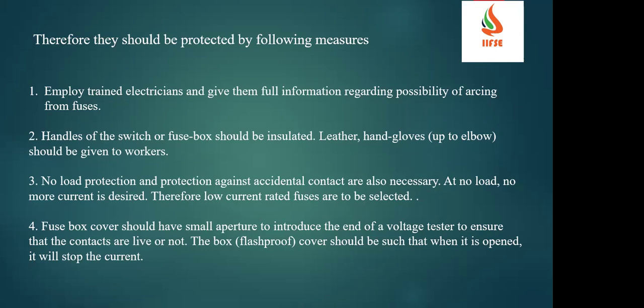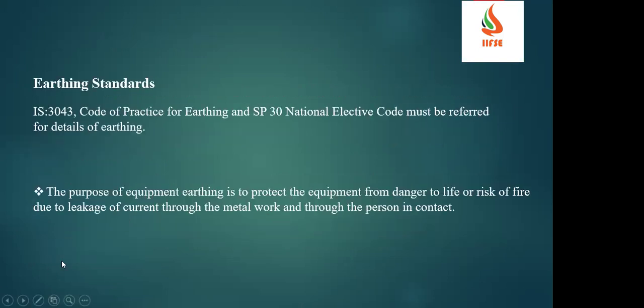It gets tripped properly. The fuse box cover should have a small aperture to introduce the end of the voltage tester to ensure whether the contacts are alive or not. And the box flash proof cover should be such that when it is opened, it will stop the current. It is about the interlocking system. The earthing standards: IS 3043, the code of practice for earthing, and also the National Electrical Code SP30. You can refer to them for more technical detail about earthing.